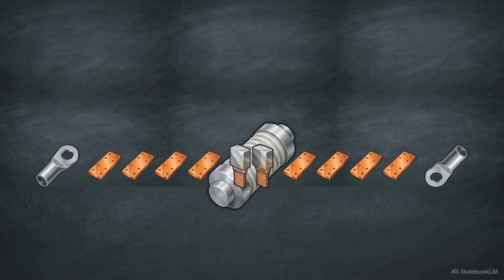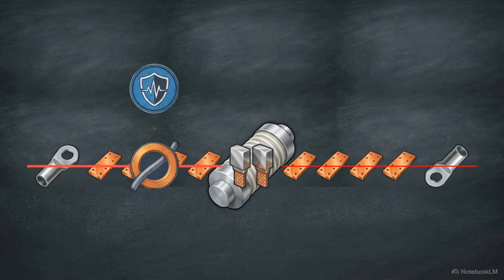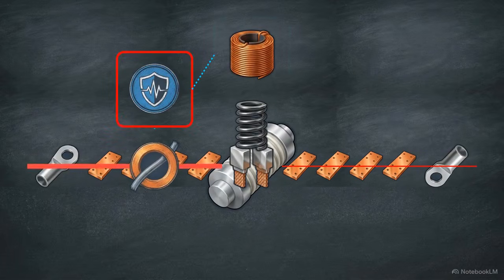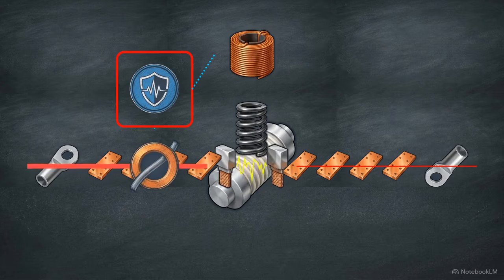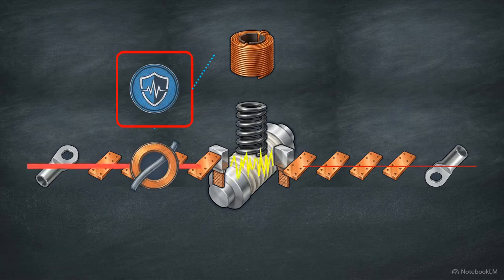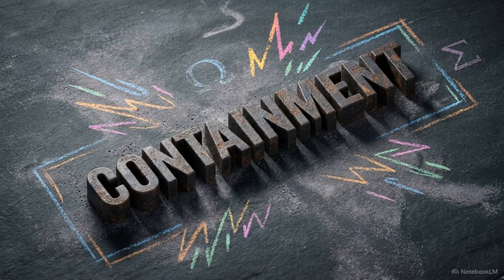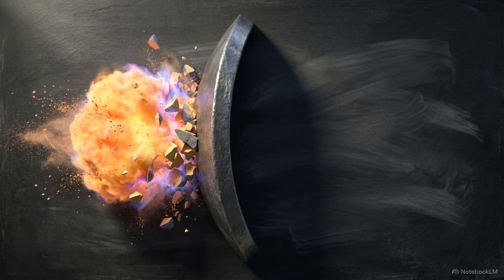When the protective relays detect the massive current spike, they signal the breaker to trip. Heavy internal springs forcefully pull the physical contacts apart, stretching the electrical arc inside a chamber of vacuum or inert gas until the plasma chokes out. It is a purely brute force physical solution, and its success depends entirely on one single factor. The mechanical strength of the breaker housing must exceed the explosive energy of the fault itself.